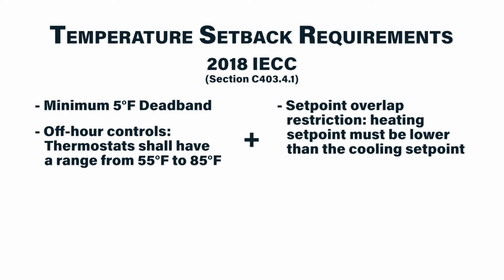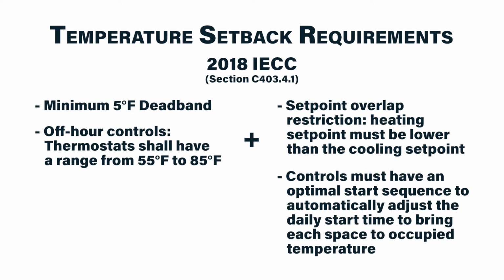The other 2018 code update is to have an optimal start sequence. This means that your HVAC system will automatically adjust the time it starts every day to warm up or cool down the building. That way, on mild mornings, the system won't run as much, but on extreme days, the system might start really early to give the building time to get to its occupied temperature set point.